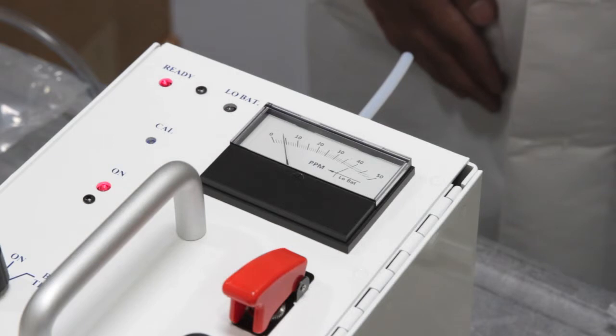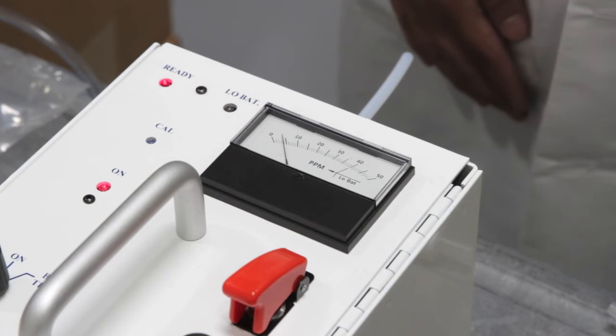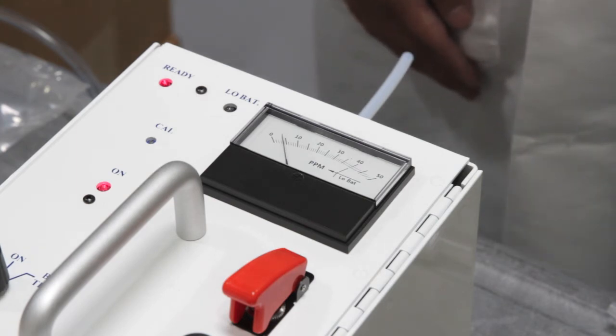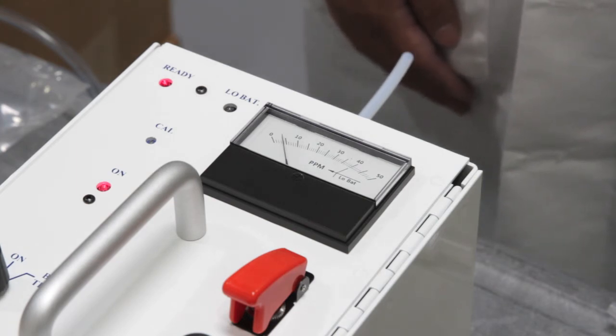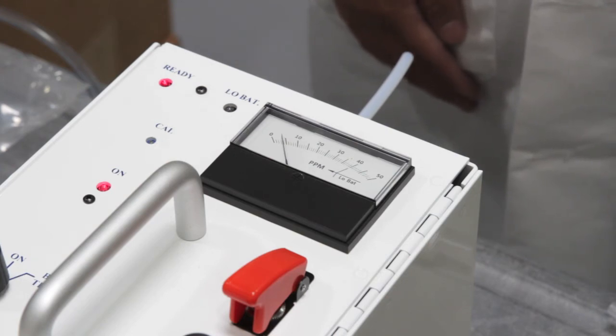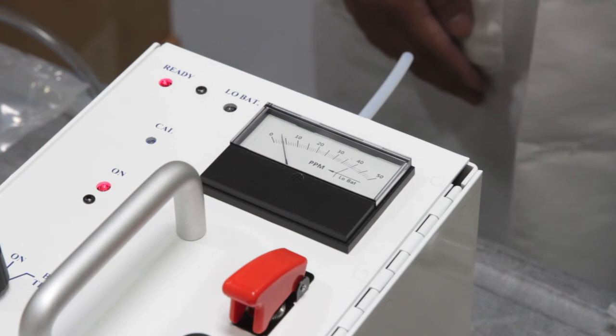Readings can sometimes jump when the sample bag is disconnected and then drop down. This is a normal condition which occurs due to changes in pressure. The recovery from a reading is about 120 seconds to 20% of the reading, depending on the age of the sensor. Full recovery to 0 may occur within 120 seconds, depending on the age of the sensor. Your calibration is now complete.